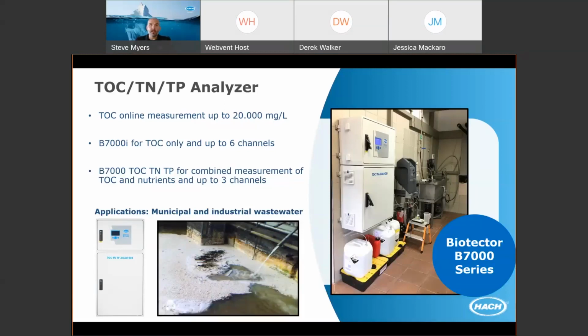It's available to be configured for TOC only if organics is your main concern, but there's also the potential to add on total nitrogen and or total phosphorus as a measurement internally to this unit. So it's possible to configure these to measure multiple sources of influent as well. If you have the ability or location to and desire to monitor multiple sources, these can be set up to sequence between multiple channels, 6 for the TOC only and up to 3 for the TOC with TN and or TP as well.